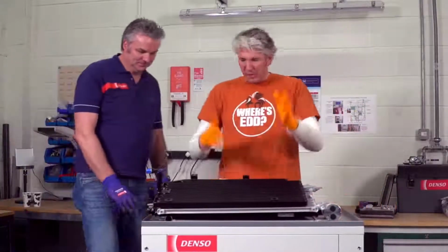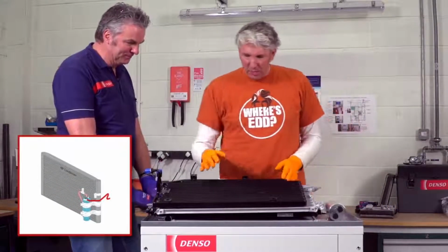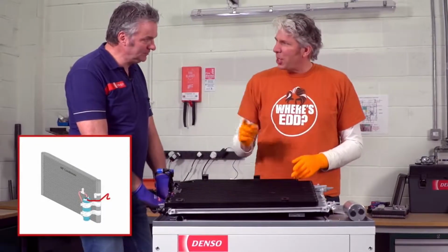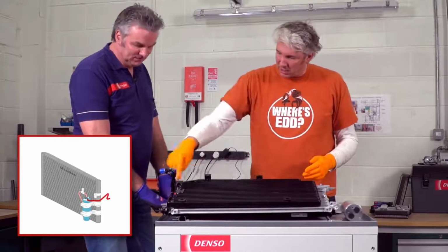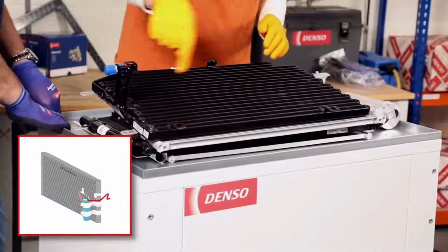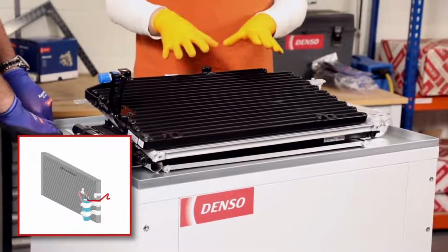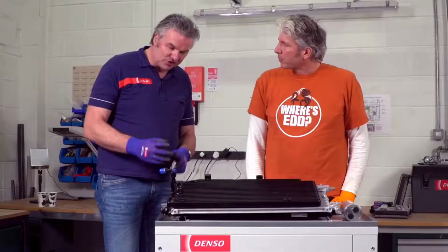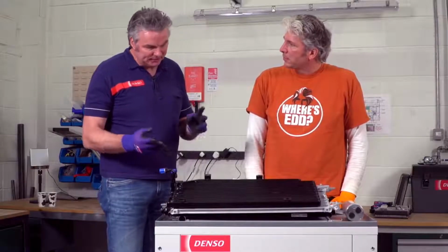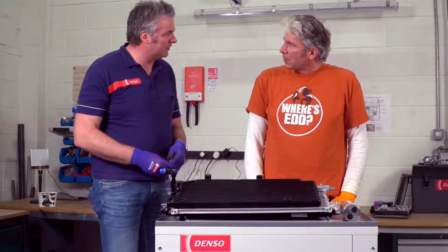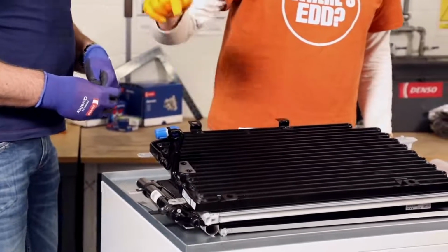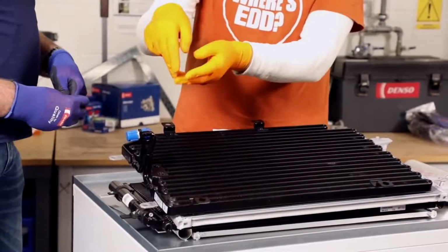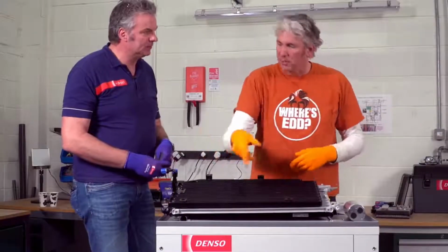So condensers. We have a nice big stack of condensers. Now, obviously, this is the serpentine condenser, and that's because it looks a bit like a serpent or a snake. You can see it starts at one end and goes all the way around back to the other. But there are variations of this as well. We had the single flow serpentine, then the dual flow, and the last one was the triple flow serpentine type condenser. So instead of just going one in, one out, it would go one in, but then split into two or three branches, go around and then come back into the one.